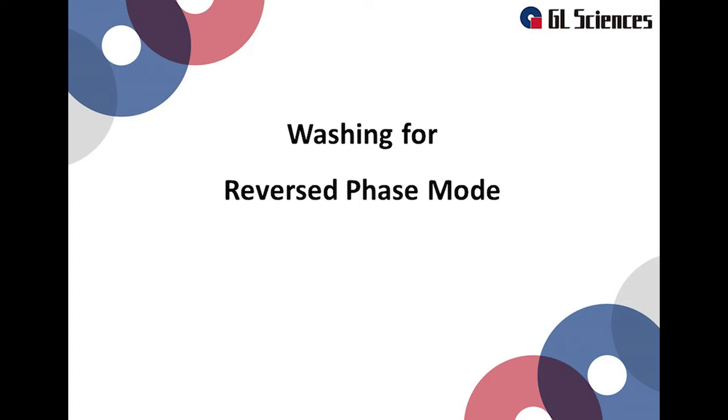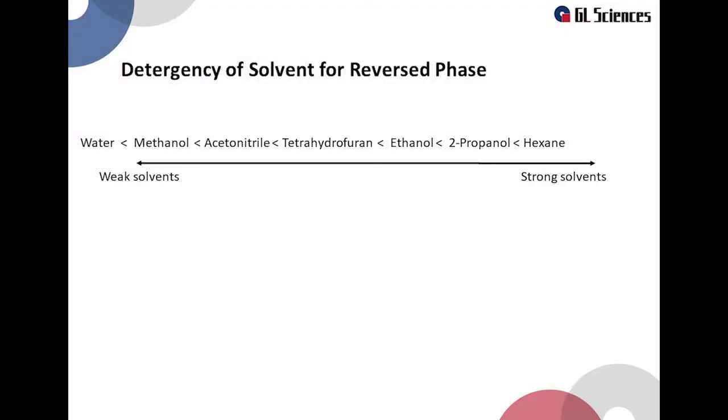Now we will explain how to wash the reversed phase mode column such as a C18 column. The solvents that are used to wash reversed phase columns have different detergent strengths. Of these, water is the weakest detergent. Hexane is the strongest detergent. A weak solvent is usually used as the mobile phase for a reversed phase column. Washing a column may require a stronger solvent.